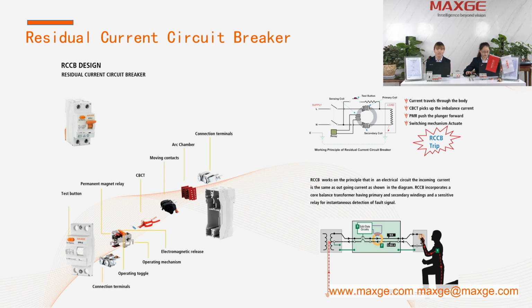RCCB works on the principle that in an electrical circuit the incoming current is the same as the outgoing current. As shown in the diagram, the RCCB combines a core balance transformer, with primary and secondary windings and a sensitivity relay, for the instantaneous detection of a fault signal.